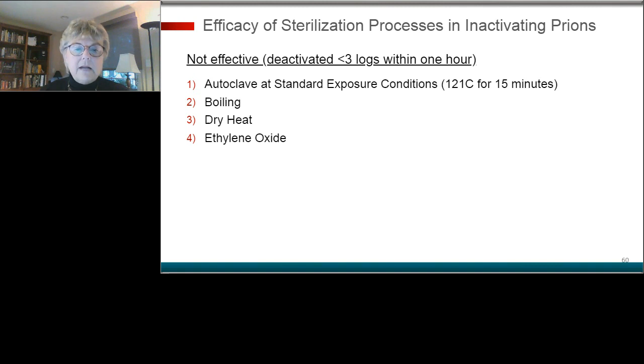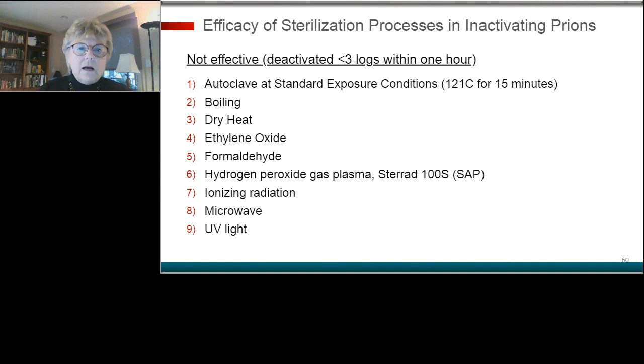The ionizing radiation and microwave and UV light. None of it would kill, but that's the wrong word. None of it would deactivate or destroy the prion protein. Those things that were effective were autoclave at 121 degrees centigrade for 1 hour using a gravity displacement sterilizer, or 121 degrees centigrade for 30 minutes with a Prevac sterilizer. Autoclave at 134 for 18 minutes with Prevac, 134 for 18 minutes immersion in water.